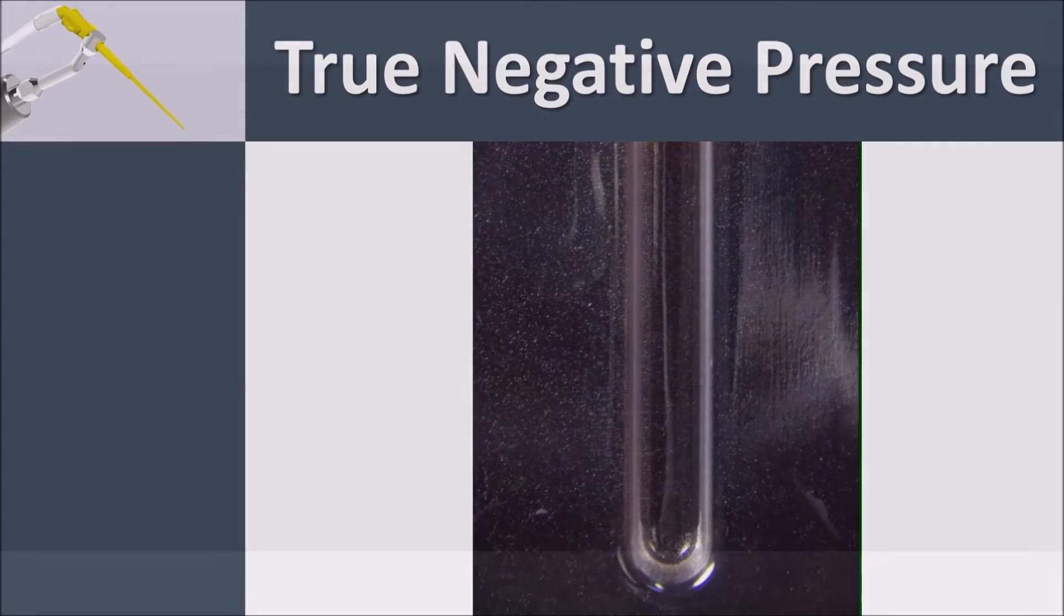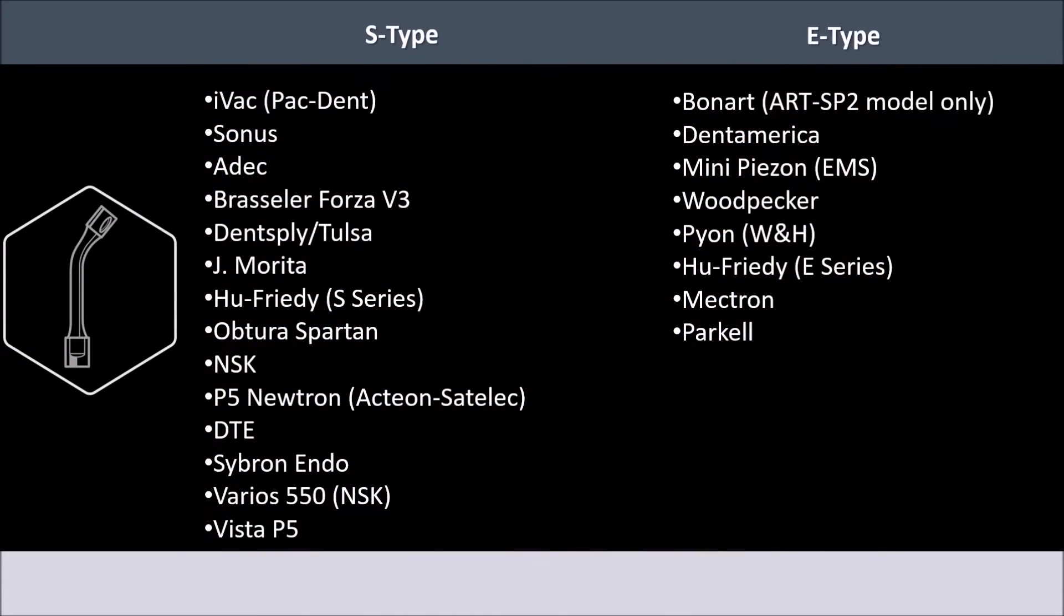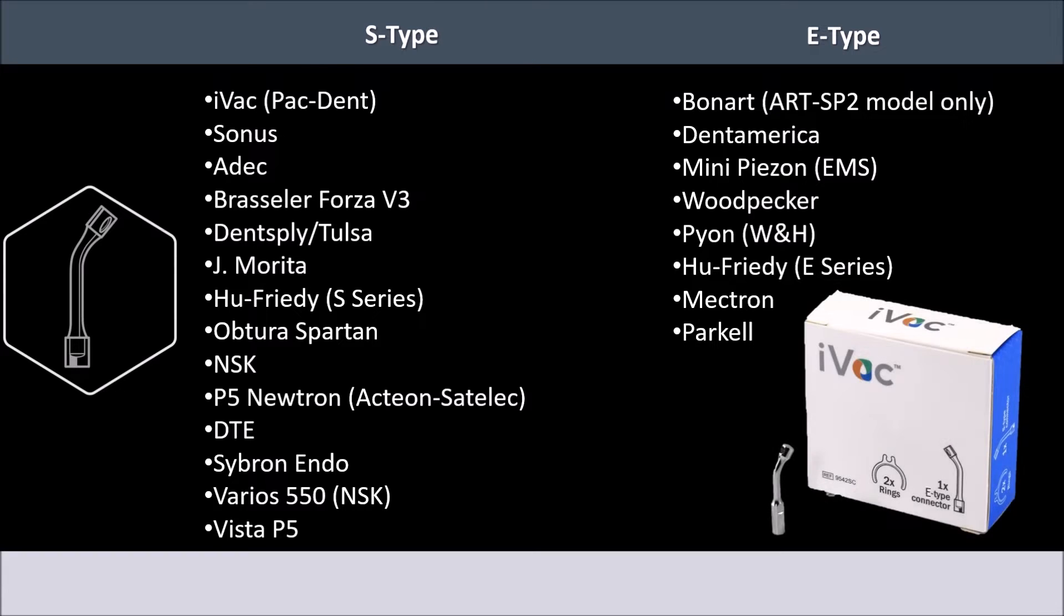If the operator does not have a piezo unit with a reservoir or if the unit is built into the equipment, syringe and cannula irrigation can be used to drip the irrigant in the pulp chamber. The iVac can be used with the two most common types of piezo units: the S-type and the E-type. The S-type connector comes in the intro kit while the E-type connector is offered separately.